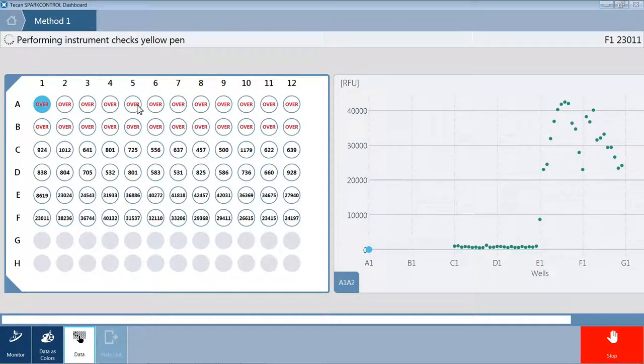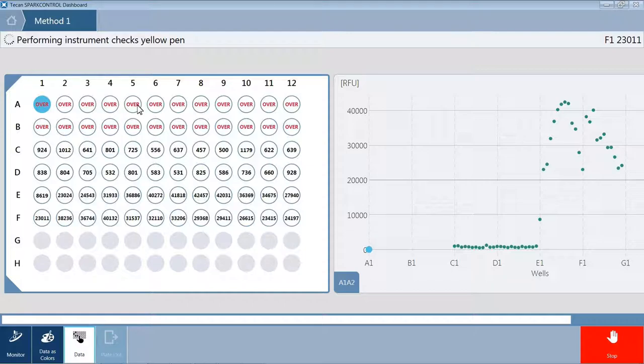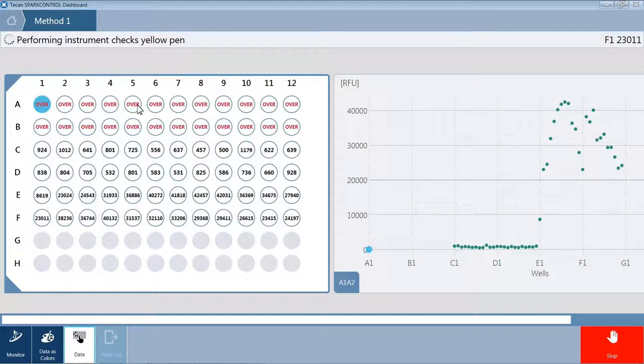For the orange highlighter pen in rows A and B, a strategy for lowering the intensity there to something more acceptable would be to reduce the bandwidth on excitation and/or emission, to lower the gain, or to move the excitation or the emission wavelengths, maybe even both, to something that are less ideal.